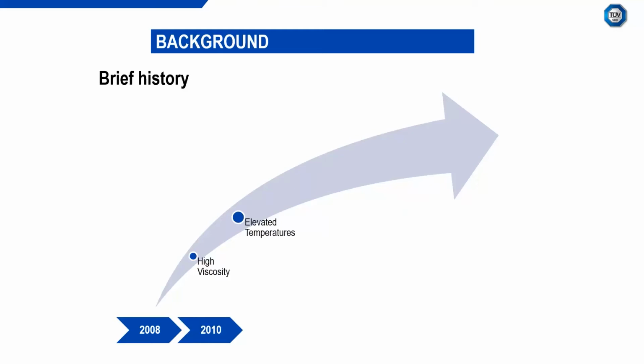But back in 2010, we were approached by an oil and gas operator in the North Sea who was swapping out their turbine meters for Coriolis devices. And they were operating at elevated temperatures, typically in the region of about 70 degrees Celsius. Now, historically, calibration laboratories such as NEL and those located all around the world normally operate close to ambient, around between 15 to 25 degrees Celsius, although many, including NEL, can operate at higher, up to about 40, 50 degrees Celsius.